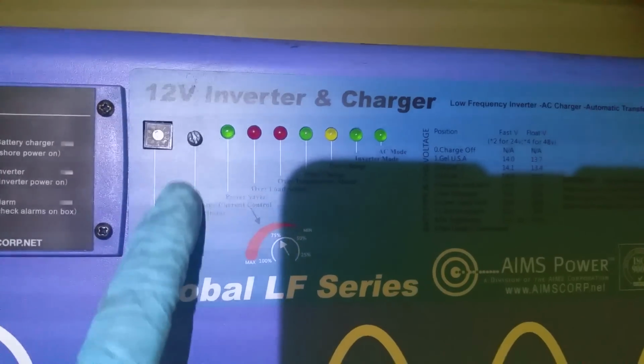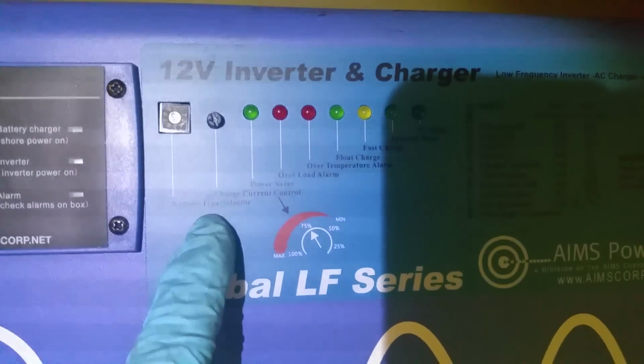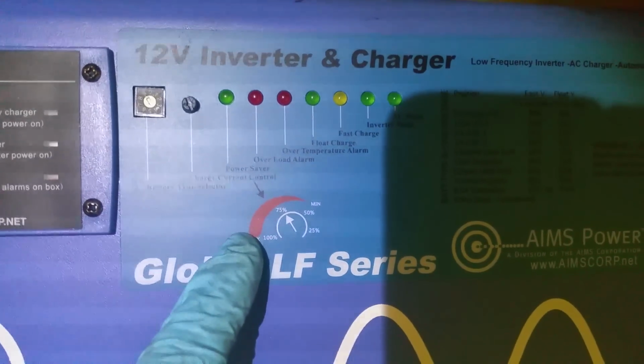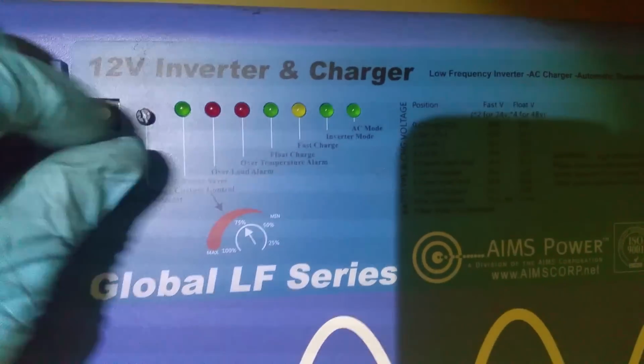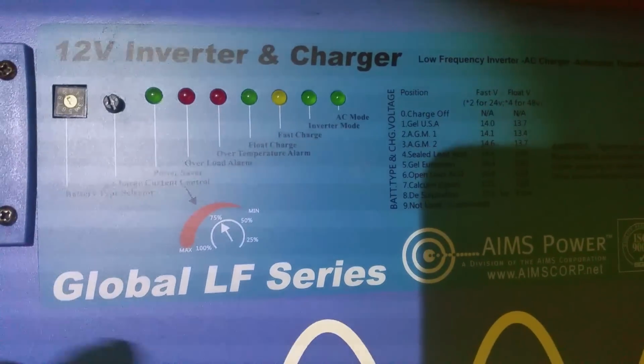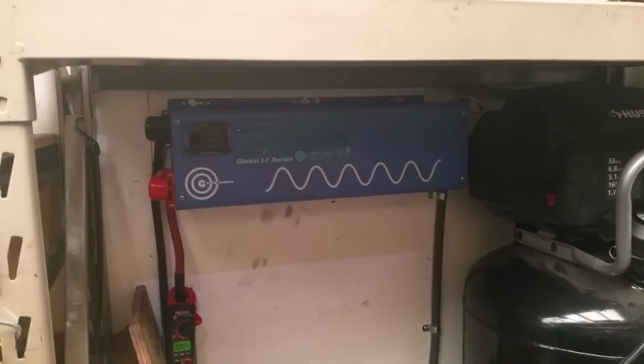And then this little dial right here is actually your charge selector. Now I didn't really get this at first, because I didn't have the battery charger hooked up right away. But essentially, if you have it all the way to the right, it maxes out your battery charging capability, 100%, so that's 100 amps. If you have it down all the way, it'll max out at about 25 amps. Now you can adjust that if you want a higher charge rate. It goes into 3 different stages of automatic charging, a high charge and then a kind of a medium charge, I forget what they refer to in the manual, and then a float charge to keep the batteries maintained.